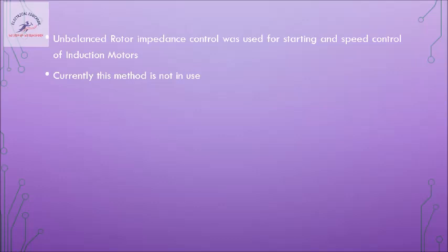Now, because of continuous use of motors, wear and tear or frictional reasons, it is possible that the physical structure of the rotor may change over time. The rotor bars are connected to the rotor rings; if you imagine the construction of a squirrel cage or a slip ring rotor, and there is a loose contact in the rotor circuit, we are talking about a loose contact, not an open circuit. Then it will alter the effective area of cross section of a conductor.